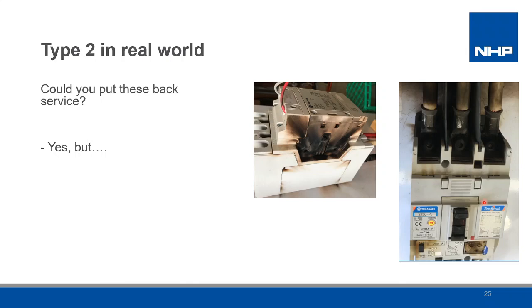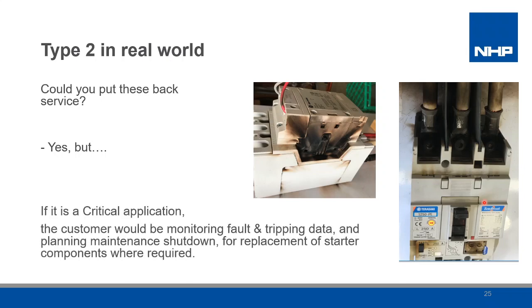However, it is wise to schedule a maintenance inspection during a plant maintenance shutdown period, as once on site, when a starter combination has been in service for a long period of time and there has been some MCCB trips and the contactor has been subject to some DOL starts, the performance can differ. With maintenance procedures and Type 2 selected components, these will provide the end customer minimal downtime and minimal lost production in the event of a short circuit fault occurring. Plus, if you are replacing a motor, verify that the starter components are suitable for the new motor, especially if an IE3 motor is being installed.